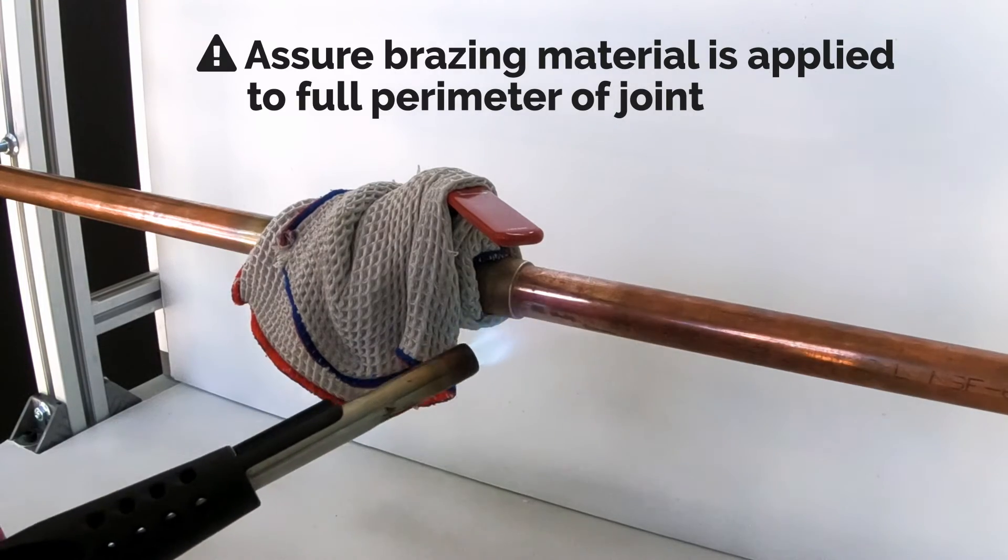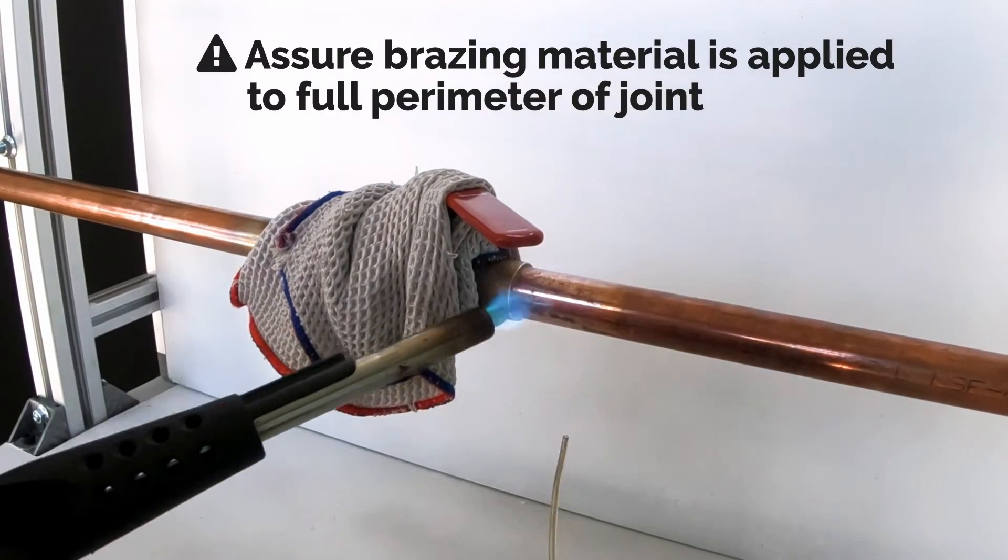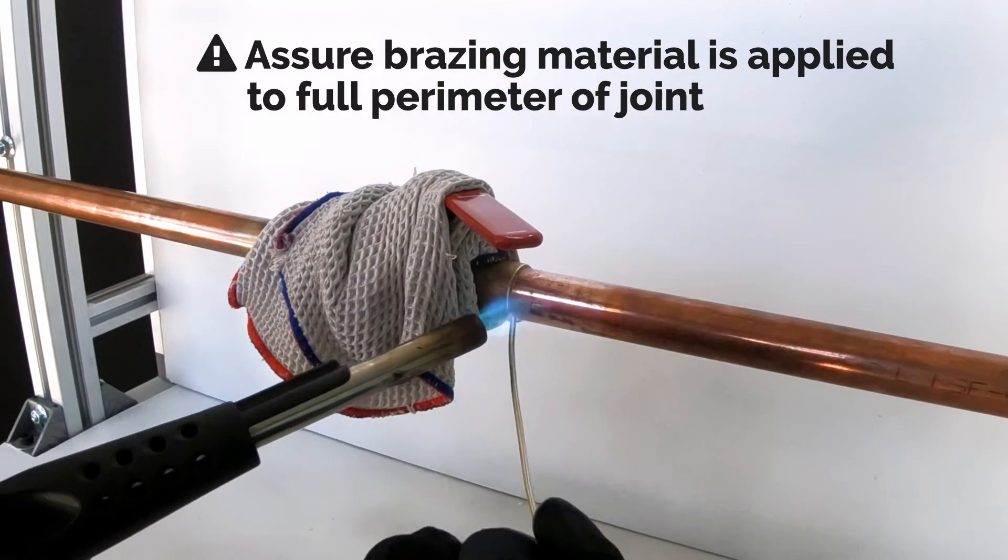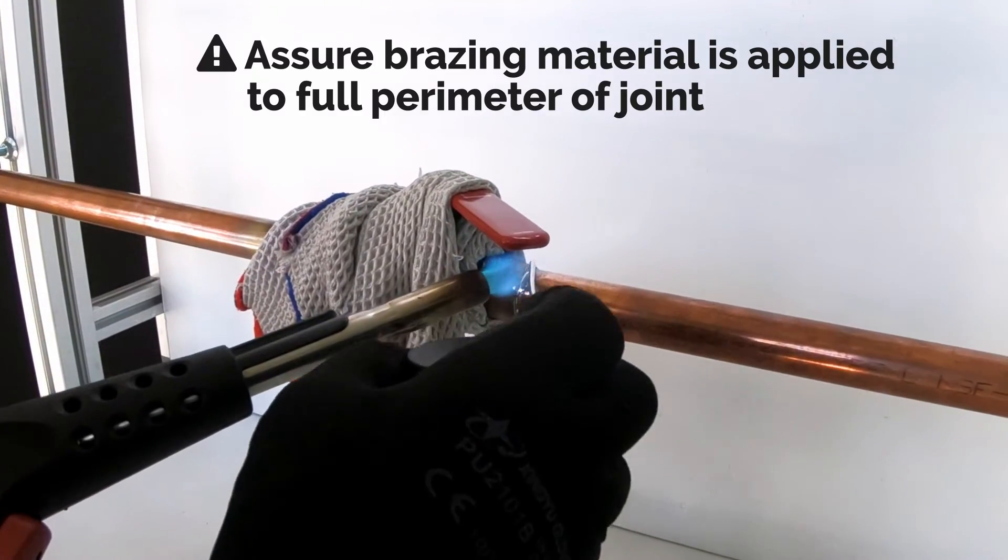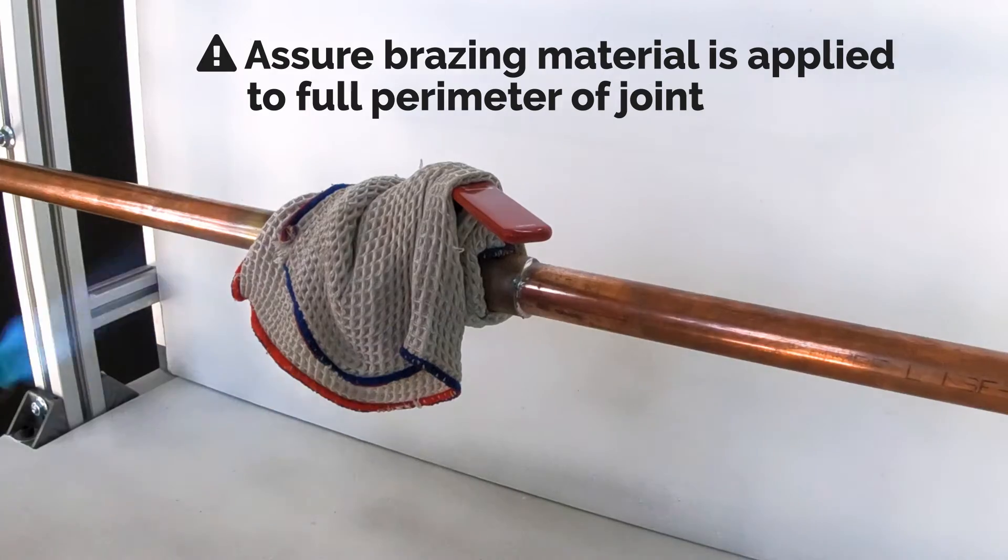For installations in vertical positions, make a similar sequence. At the end of the process, it is necessary to allow valve to cool naturally and not use water or other fluid to expedite the cooling.